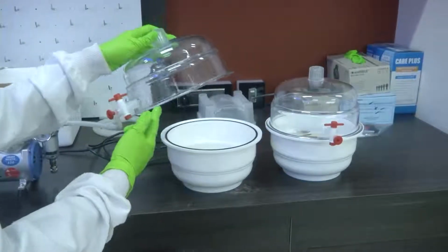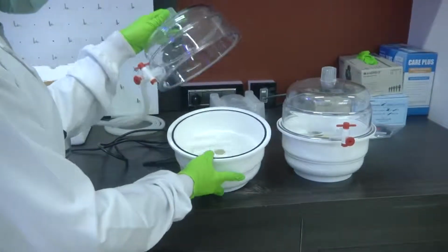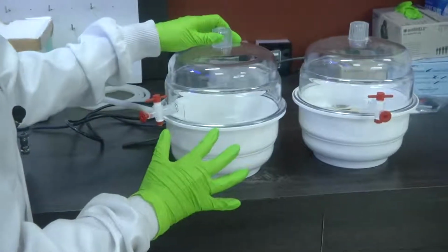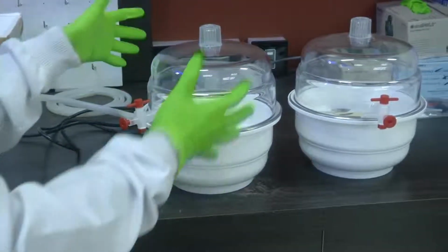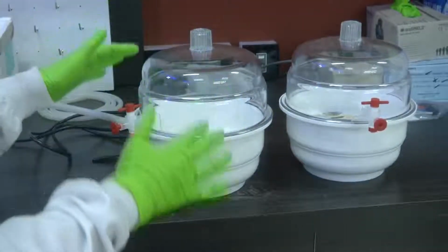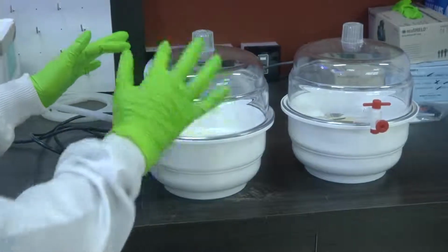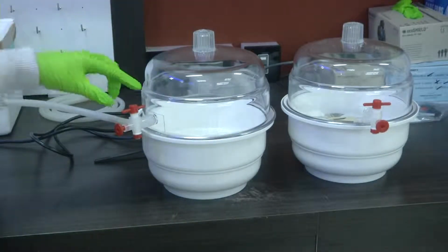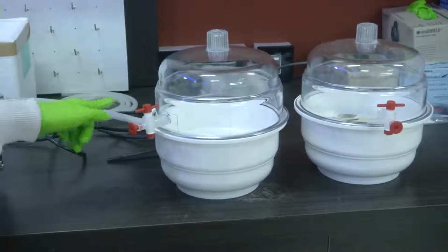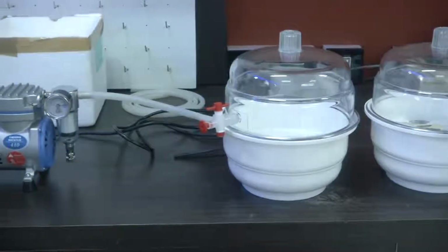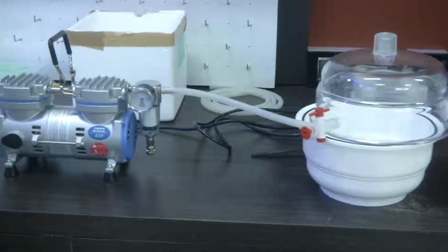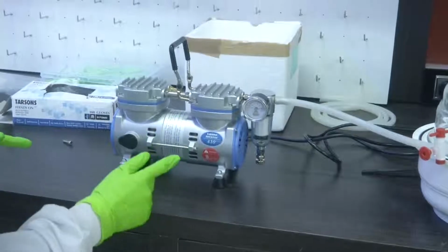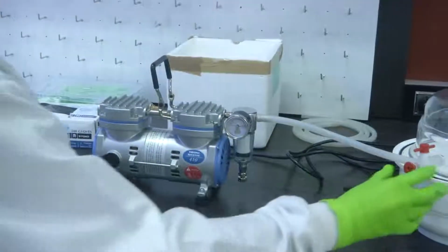If you could see this, it has a ring-like structure which forms a sealant and creates a vacuum space inside the chamber. So there is no air or moisture inside the chamber when you compare it to the outside environment. The chamber has a valve to open and close, and this is the tube which goes into the pump. The pump has a dial gauge for us to see how much pressure has been maintained.